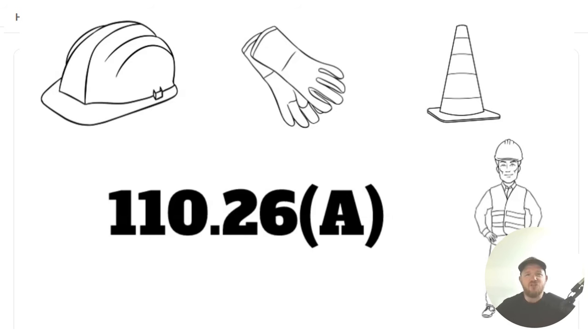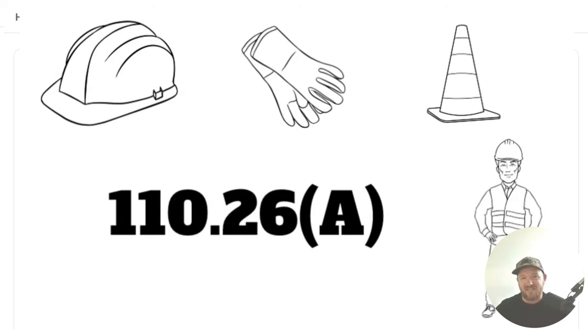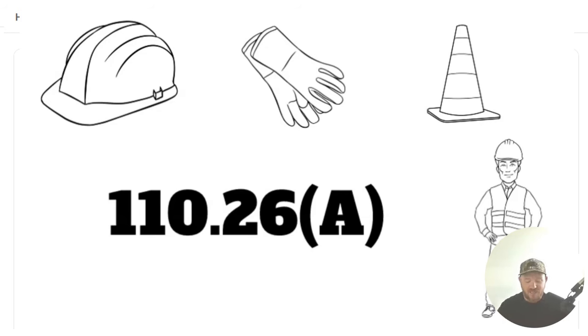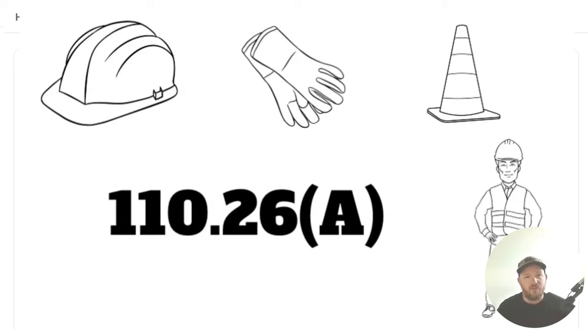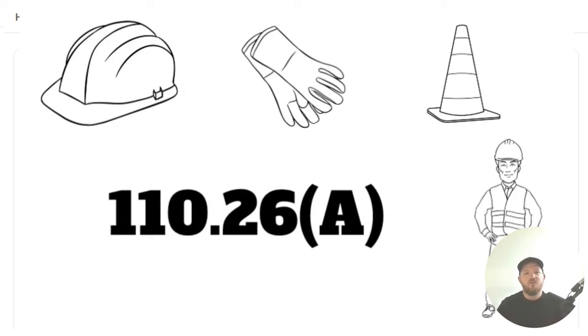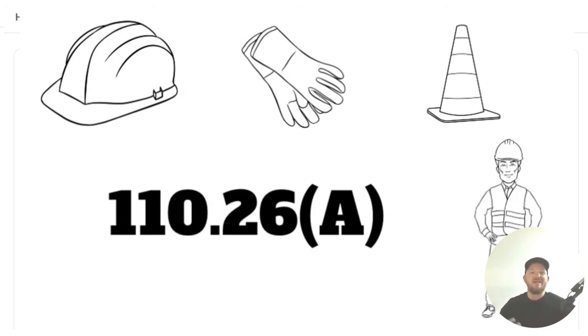But did you know that all electrical equipment is required to have working space and access? Let's go back to the beginning in 110.26. It says access and working space shall be provided and maintained about all electrical equipment. And at that point, it doesn't give any dimensions yet.